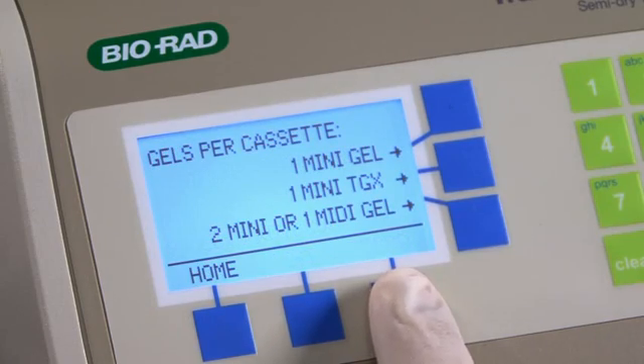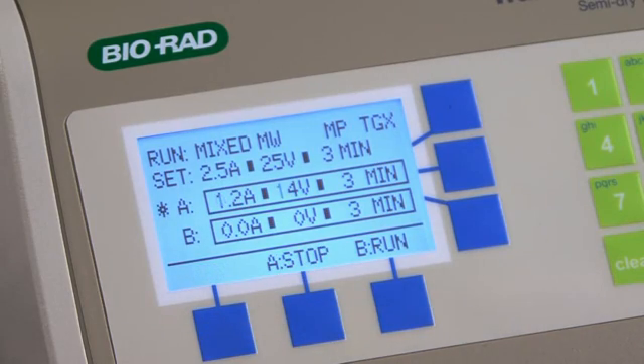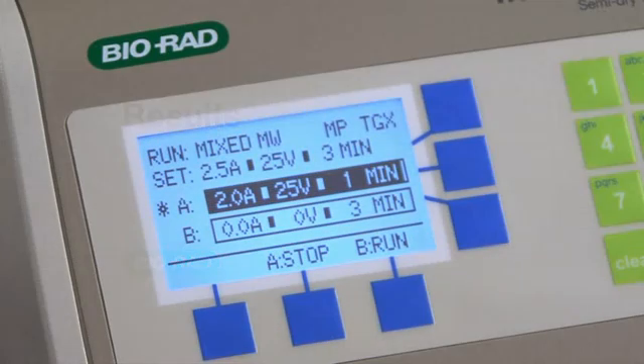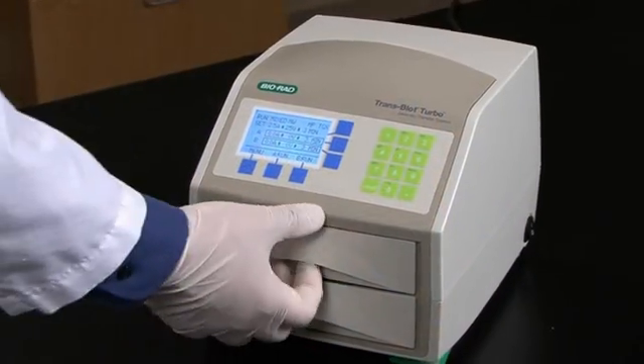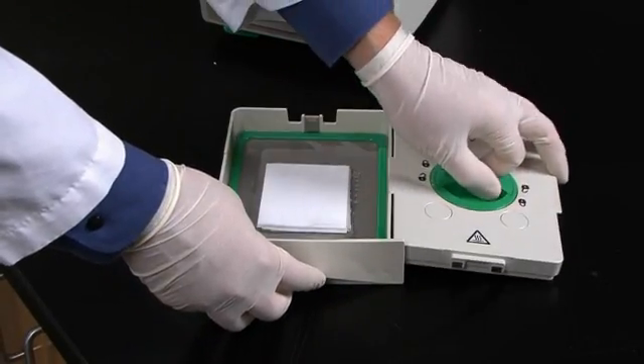If you are using Bio-Rad Mini-PROTEAN TGX gels, you can use the TGX Turbo protocol that provides efficient transfer of one mini TGX gel per cassette in 3 minutes. After the run is complete, the unit will emit a beep, and Run Complete will be displayed on the LCD screen. The blot does not have to be taken out immediately, though we do recommend proceeding with blot detection as soon as is convenient.